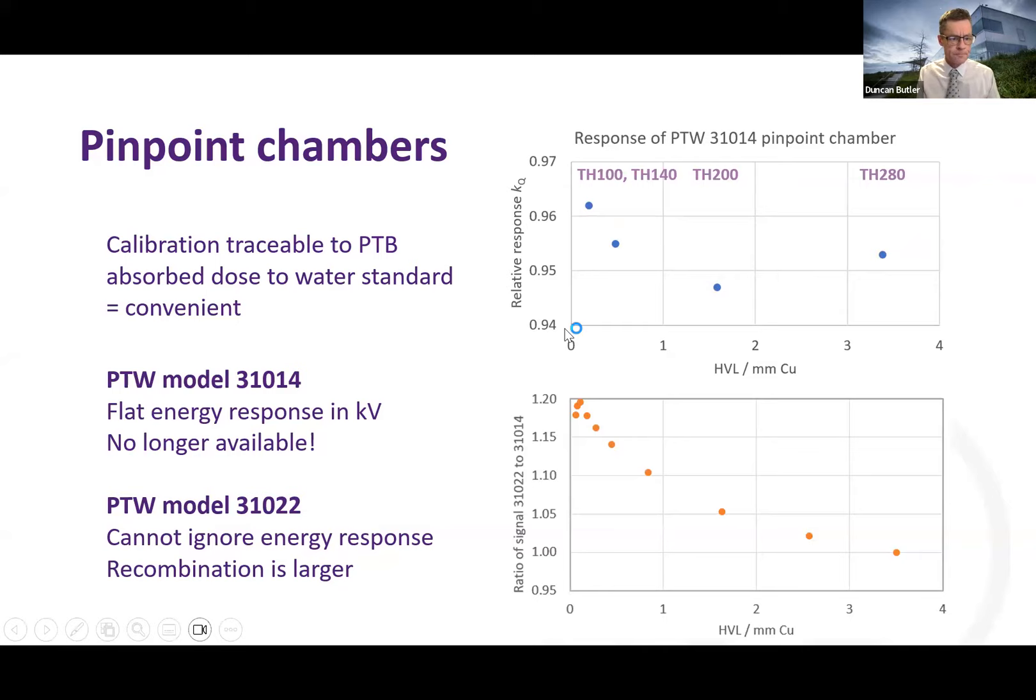Generally if you use four beams from 100 kV to 280 kV, and in this plot you can see that there is a bit of energy response, but it's within about 1% over the whole kV range. So you can really use this chamber without much of a correction factor. That's the model 31014 pinpoint chamber. Unfortunately it's no longer available, and the replacement 31022 has a stronger energy response. And in the bottom graph I've plotted the ratio between those two chambers in air for conventional beams, and there is a 10% energy response for the 31022. So you can still use it but you have to be careful to correct the energy response. Also the recombination for this chamber is quite a bit larger.